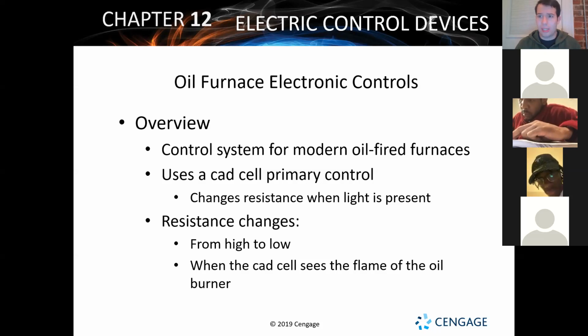So a CAD cell, CAD stands for cadmium sulfide. You don't need to know that, but what it's going to do is, as opposed to any of the other switches that we've looked at so far, any other switches you've seen in the class have reacted to either a manual switch, they've been temperature controlled, pressure controlled, or looking for a float switch for a water level, or something like that. A CAD cell, however, looks for light. Literal light is what it's going to look at. And you can actually test resistance on a CAD cell and see if it's working by introducing and denying light to it.